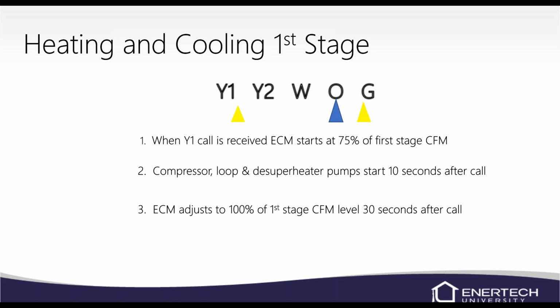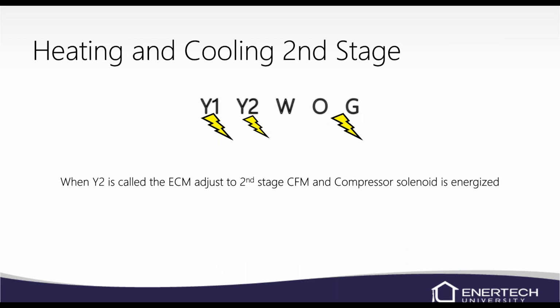Now, you may not be able to tell that it's gone from 75 to 100%. You may not be able to hear that, but you should be able to count it on your ECM board, and it'll tell you the CFM. Obviously, O will be energized in cooling mode. In second stage, once it sees that Y2 call, it will immediately adjust its CFM level to second stage, and then your compressor solenoid will be energized as well.